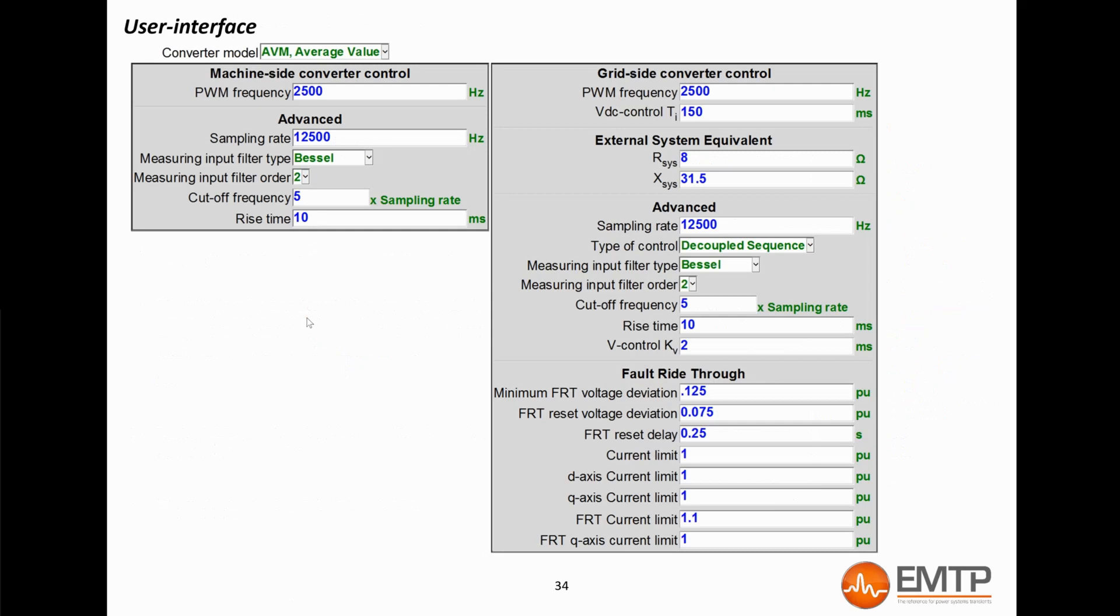Here is the user interface of the full converter mask. On the left side, you can set up the parameters related to the machine-side converter, the PWM frequency, the sampling rate, the measurement filter parameters, and the rise time for the inner loop. On the right side, you have the grid-side converter parameters, the PWM frequency, the speed for the DC outer loop control, the external system equivalent, which is the impedance of the transmission grid the park is connected to, and which is used to determine the PI controller gain of the inner loop. We explained that in a previous slide. The sampling rate, the type of control, this will be discussed in another video. The filtered measurement parameters, the V-loop gain, as explained in a previous slide, and the fault-ride-through characteristics.